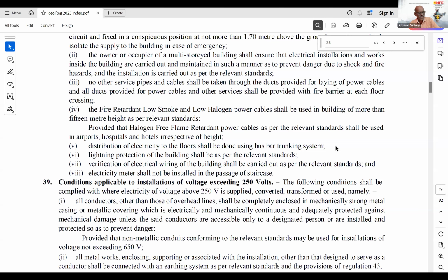Regarding the metering provisions, these are all commercial items. I am happy that I learned that MSEB, or Maharashtra state, has come to a decision to provide a meter at the flat consumer premises itself. So it will be a helping hand for the regulatory commission also to be compliant with these specific regulations, because it addresses the reduction of cable and provision of busbar trunking, especially in the ducts and rising lines. So it's a good thing that we learned from Abhijeet ji regarding the busbar trunking system.